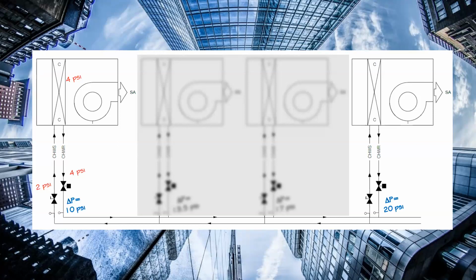That close zone at full flow, the branch near the pump, the coil will take its design pressure drop, 4. The valve was sized for a 4-pound pressure drop, and this leaves that balance valve to take up 12 pounds of pressure to equalize that branch. This is a valve authority of 4, of course 4 divided by 20 is 0.2 or 20%. This is an unfavorable valve authority, and it'll lead to control issues when the building is not at design or full flow conditions. Essentially, this will be acting as a 2-position or quick opening valve.